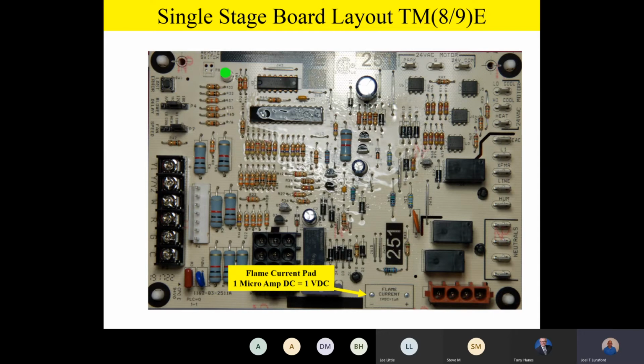So just write that down or keep that in your mind, that reading flame current on your service calls is very, very important. 3.5 to 4 is considered a normal range. At 1.5, we start generating an amber flash code to let you know there's a problem. And then at 0.1, we actually lock it out.